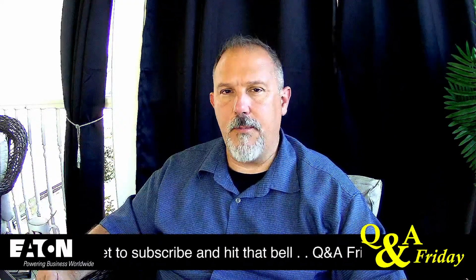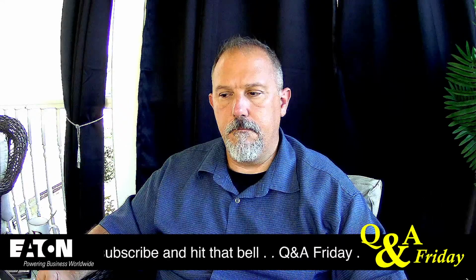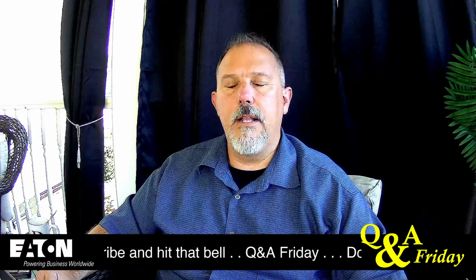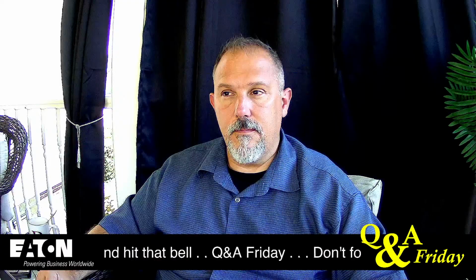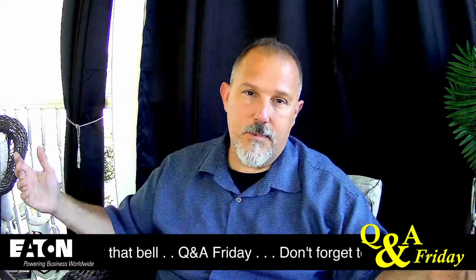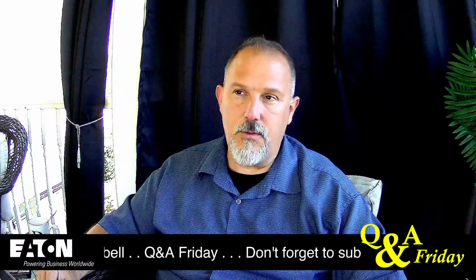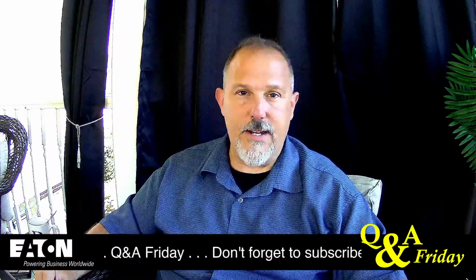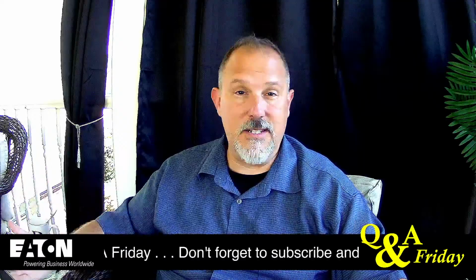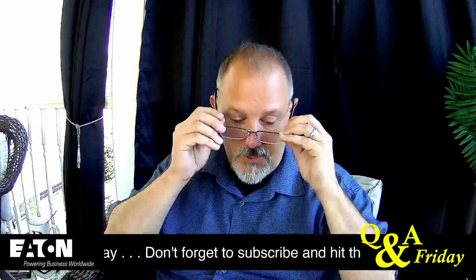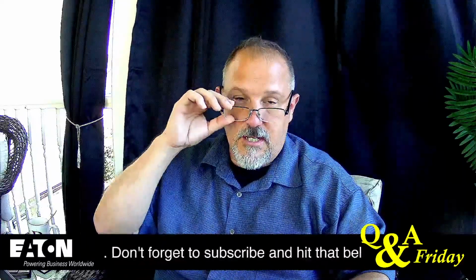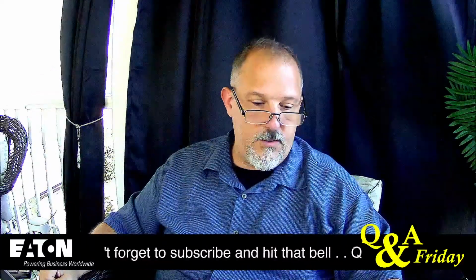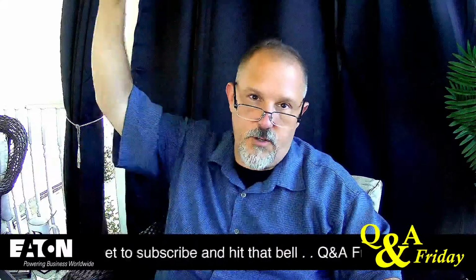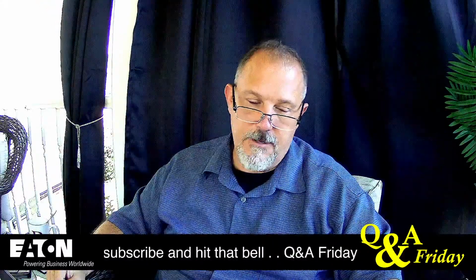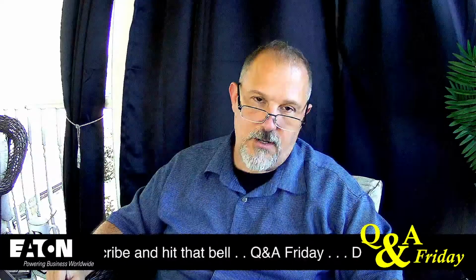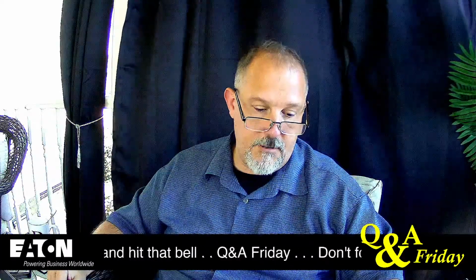It would have to be a barrier that would be listed that way. Now, there's always options to provide arc reduction technologies and things of that nature. There's a lot of different solutions, but I would say, Mr. D, that you're taking the conservative approach, which is what engineers do. We take a conservative approach and we assume worst case, and we go to the upstream overcurrent protective device. And that's what we base our incident energy on. That's the safe way to do it, in my opinion.